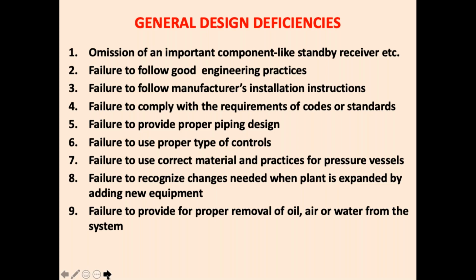Failure to use the proper type of controls; using incorrect controls also can cause problems. Failure to use correct material and practices. Failure to recognize changes needed when the plant is adding new equipment. A lot of people do expansion, and then while doing expansion, there is a problem. Failure to provide proper removal of oil, air, and water from the system, all these three things. So these are all designers' deficiencies.